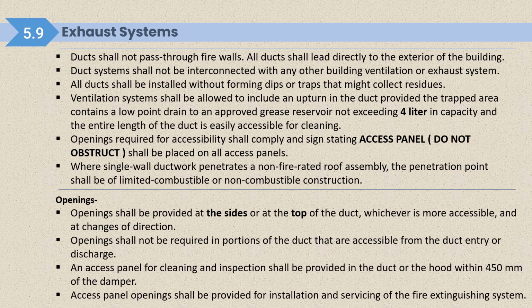An access panel for cleaning and inspection shall be provided in the duct or the hood within 450 mm of the damper. So within 450 mm of the damper, we need to provide the access panel. Access panel opening shall be provided for installation and servicing of the fire extinguishing system also. So we need to provide the access panel for servicing and maintenance purposes of the fire extinguishing system also.